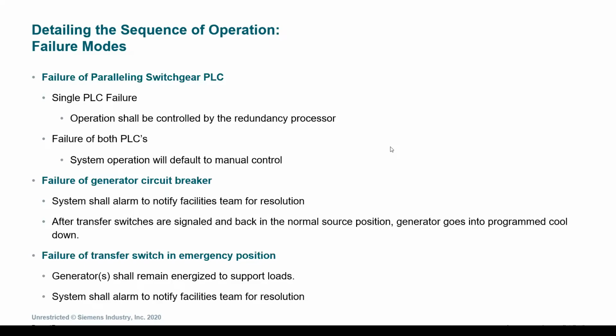Another failure that we want to talk about is a failure of a transfer switch. If the transfer switch is in the emergency position or the normal position and not able to switch one way or the other, again, if it was in the emergency position, the generator would remain energized to support the loads that are on the bus. In either case, the system would alarm and again notify the facilities team for resolution so that they can get involved and handle the situation manually if needed.